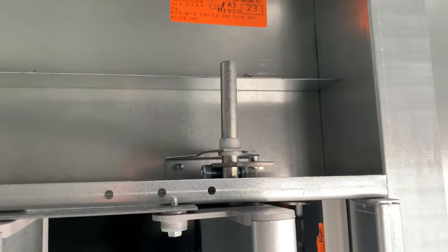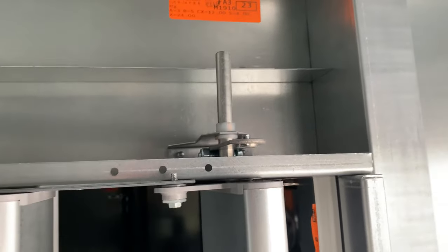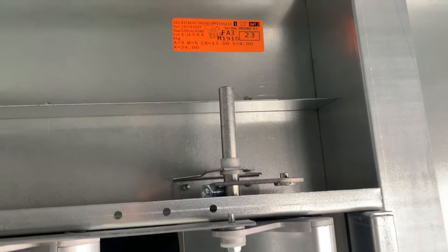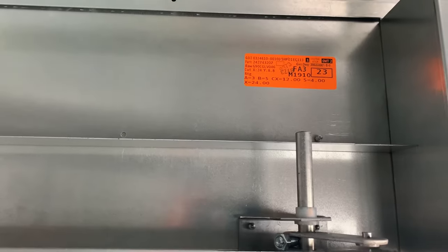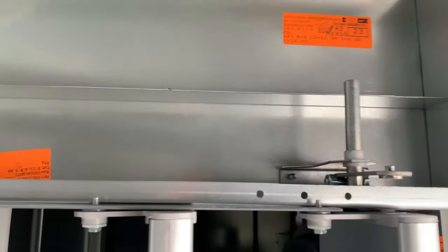Because I'm working with the mixed air, this rod right here is going to rotate either clockwise or counterclockwise. The way it's set up now, if it's going counterclockwise the damper is going to close; if it's going clockwise the damper is going to open.